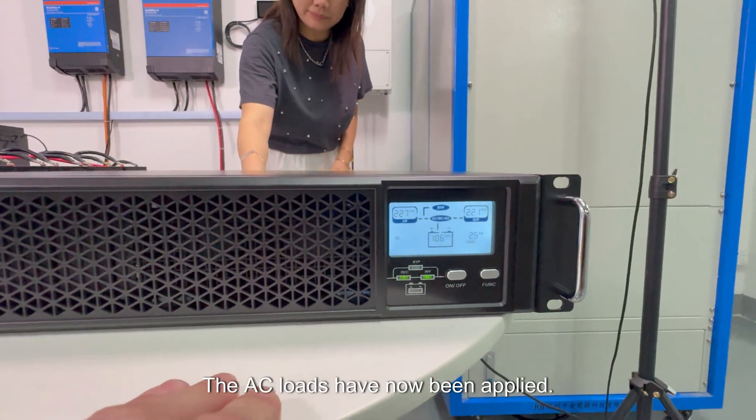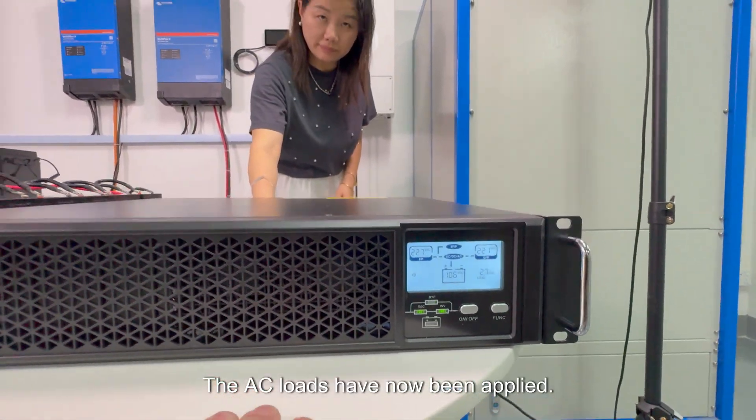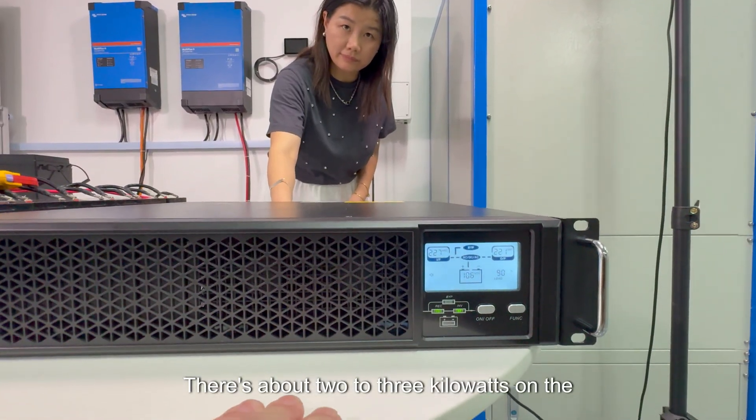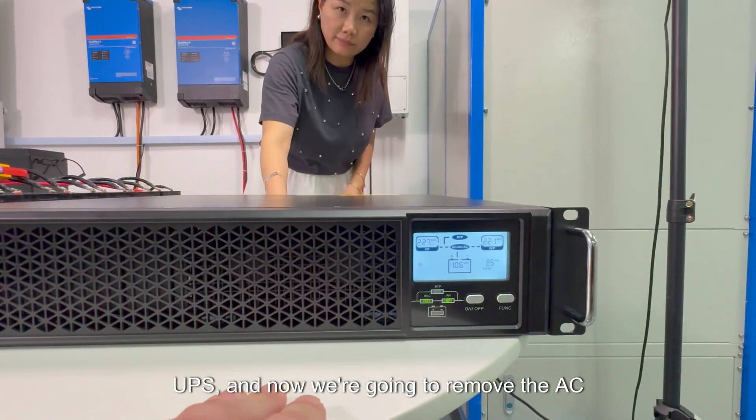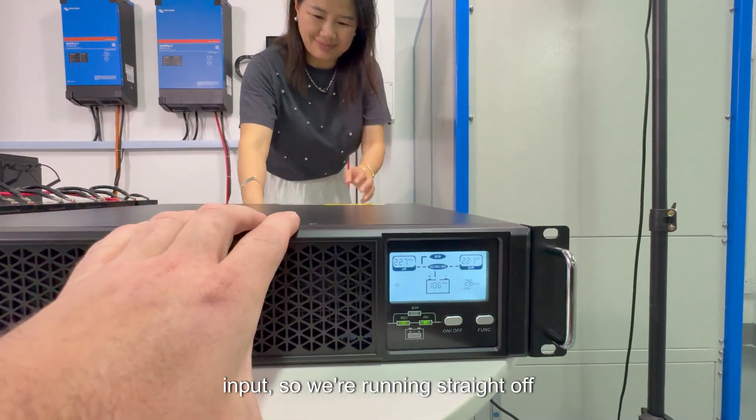The AC loads have now been applied. There's about two to three kilowatts on the UPS. And now we're going to remove the AC input, so we're running straight off battery.